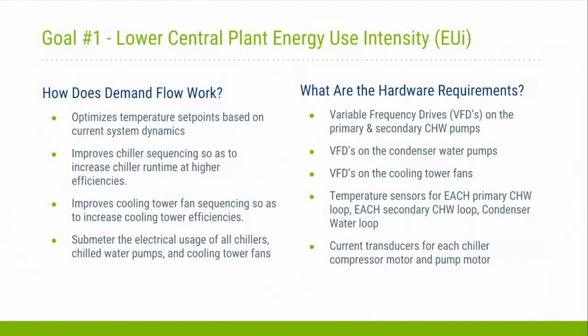Next, demand flow improves chiller sequencing so as to increase chiller runtime at higher efficiencies. That's because chiller efficiency changes based on the amount of chiller loading. Demand flow tries to increase the runtime at these higher chiller efficiencies. Next, demand flow improves the cooling tower fan sequencing. For example, 2 fans are energized at part load rather than 1 at full load, and that's more efficient.